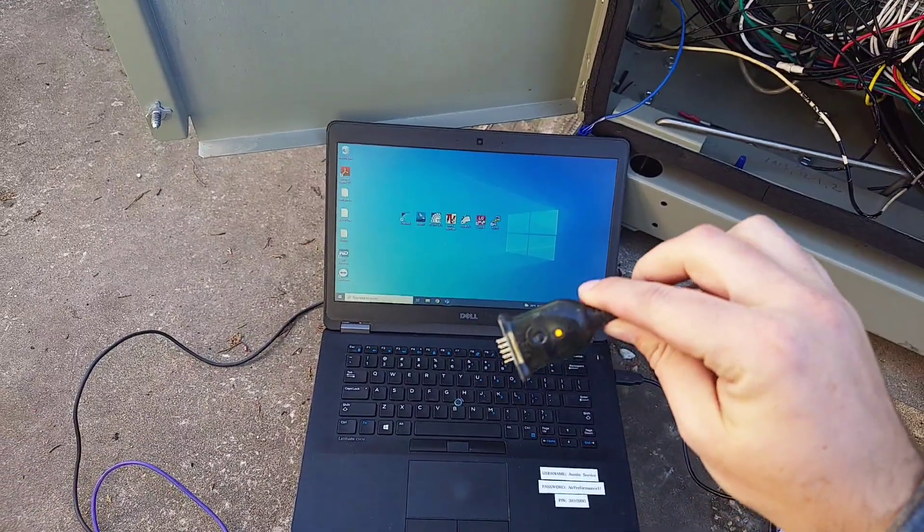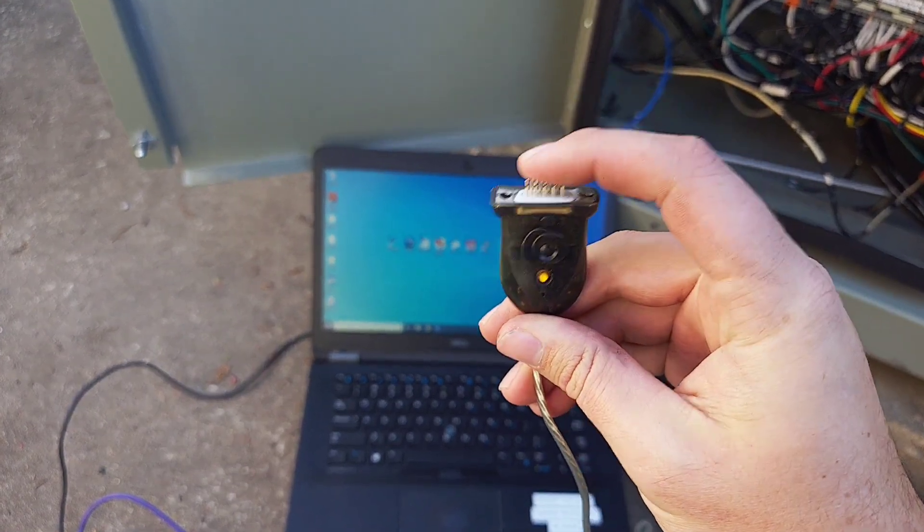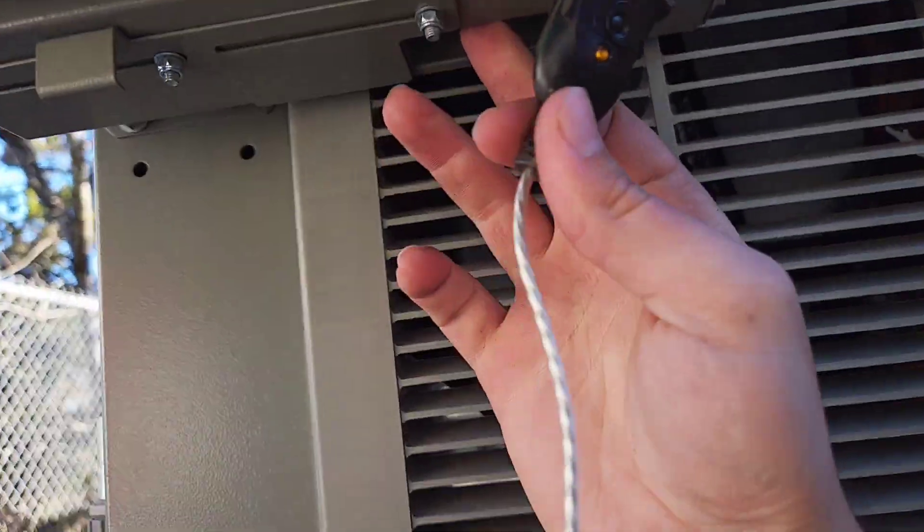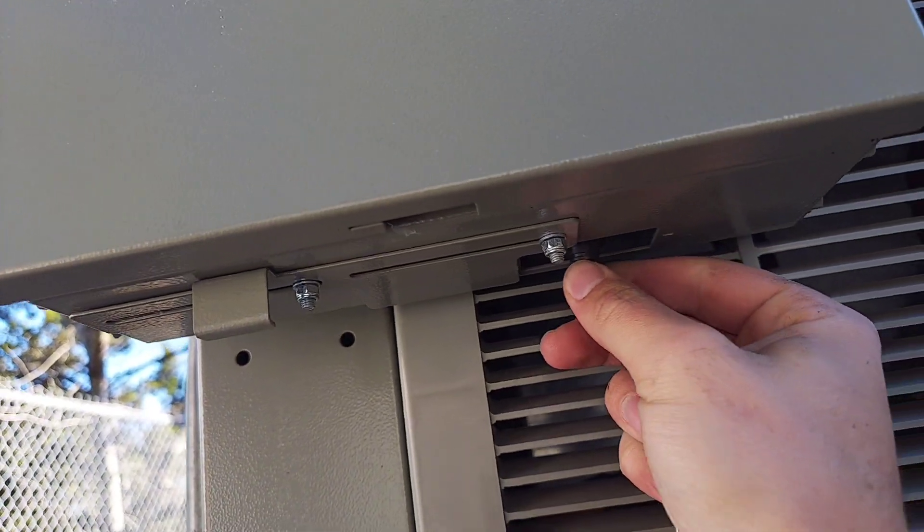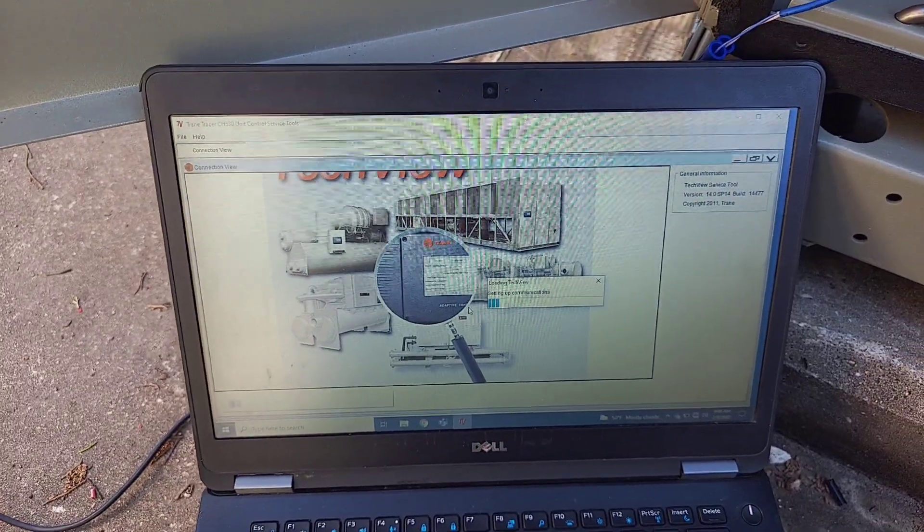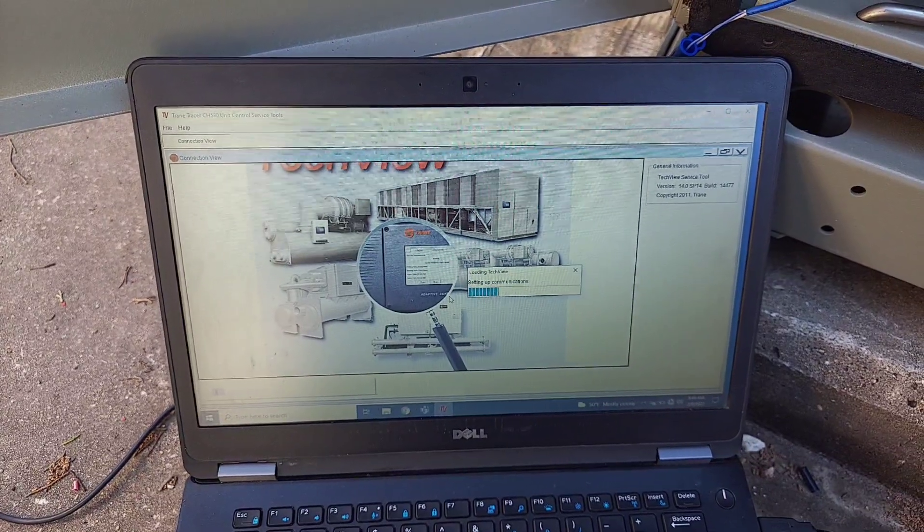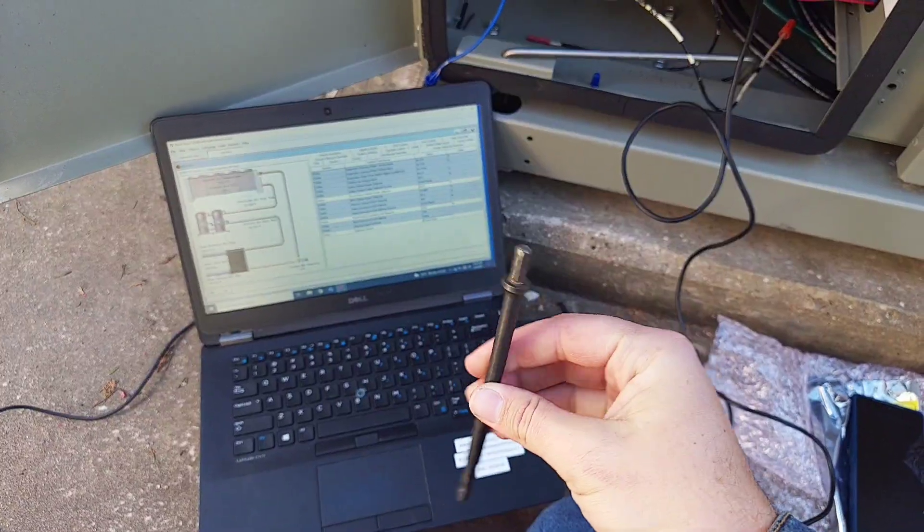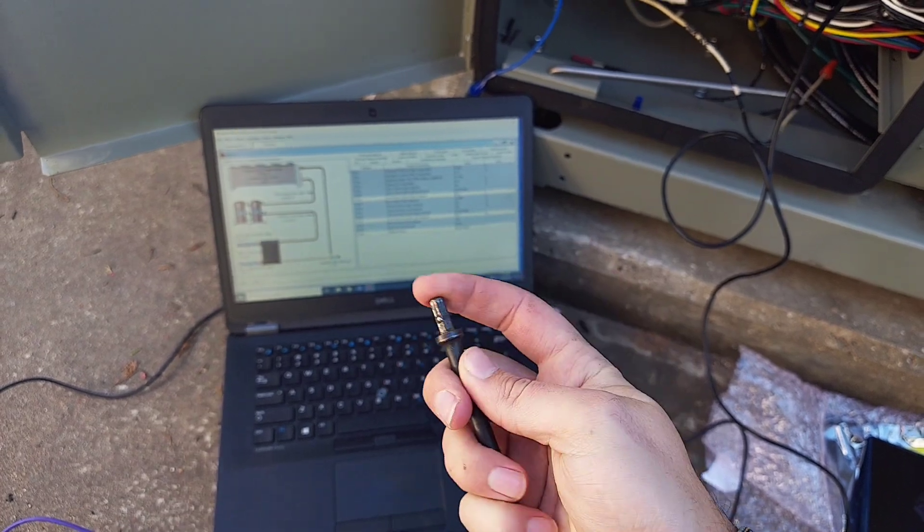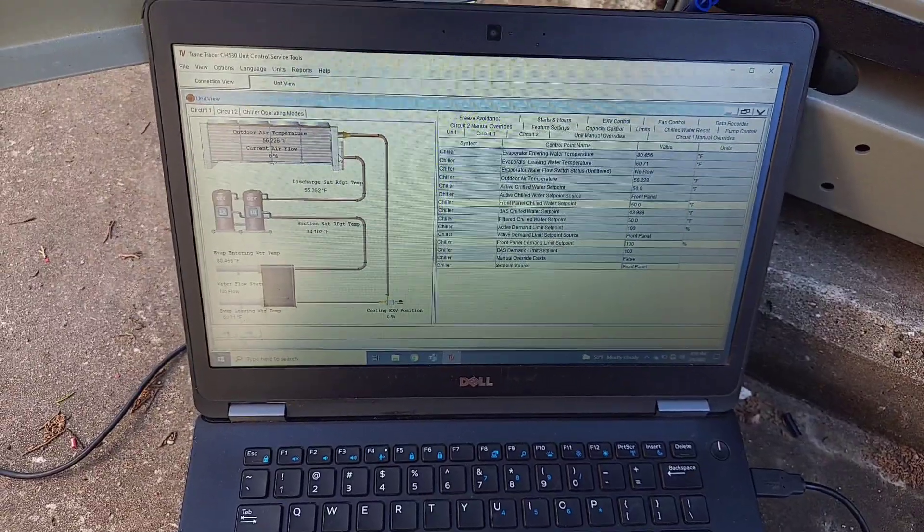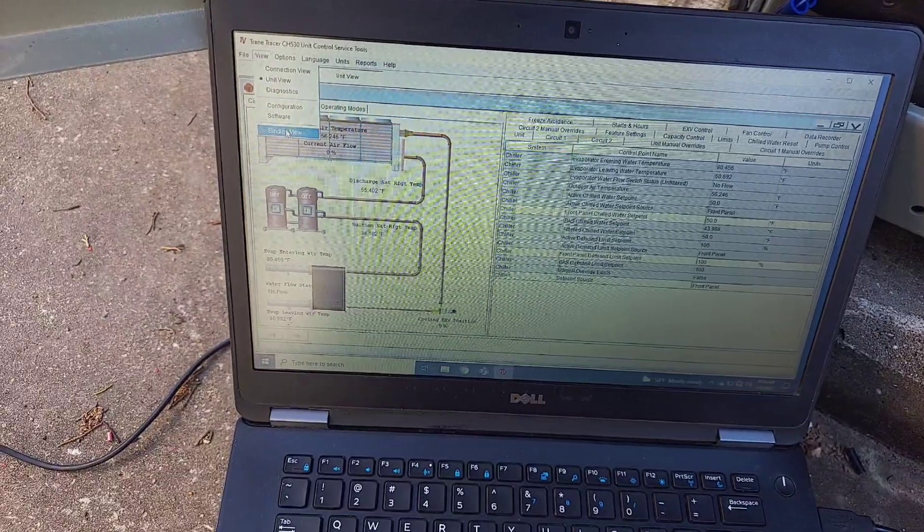We're getting our service tool set up here. This is just a serial adapter port. You can see the little pin guard's missing, but that's okay. This will plug through this bottom hole into the controller. It just lines up, pretty straightforward. We're going to go to local. Now we'll have to go into a binding view, and this will shut the machine down to do this. To do the binding, you will need a magnet. I have had really good results with the Malco tips. Just pull the head off, that magnet works perfectly. Once we get into here, we will need to go up to our views and we're going to go down to a binding view.